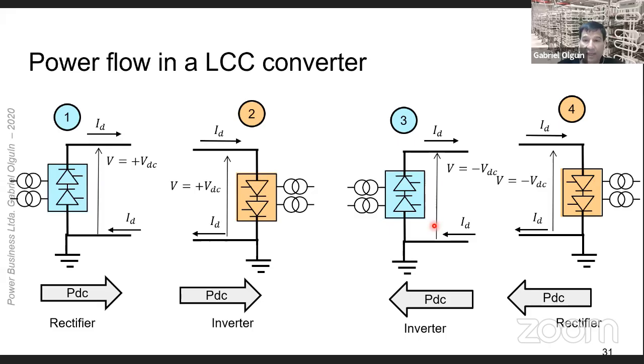Case 3 shows an LCC converter operating again as an inverter. Electric power comes from the DC link and is inverted in the converter and injected into the AC system. Case 4 shows an LCC converter operating as a rectifier. Power is taken from the AC system and injected into the DC link. It is important to note that LCC converters operate thanks to the AC voltage applied to the valves. It is actually the AC voltage that makes it possible for the valves to commutate. Hence, the inverter operation mode requires an AC system to drive commutation of the valves and current to be injected into the converter.